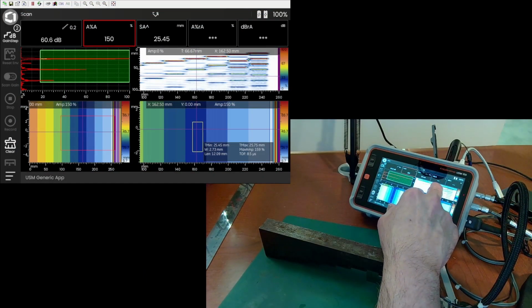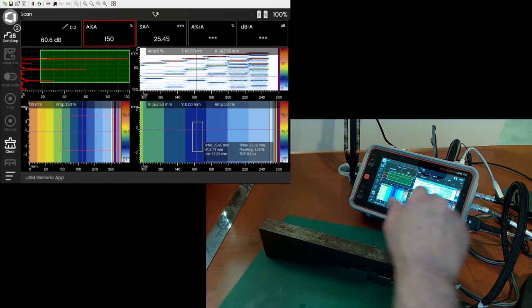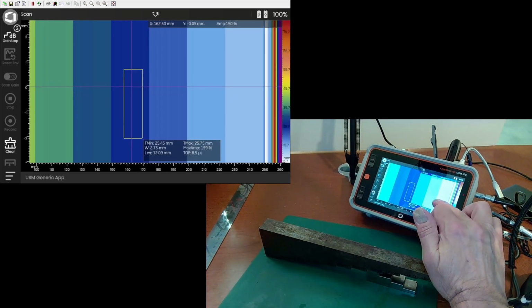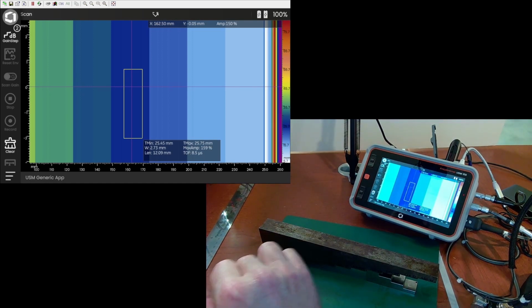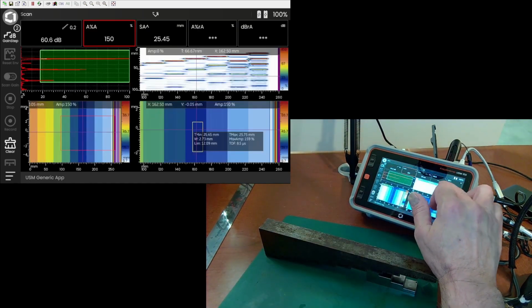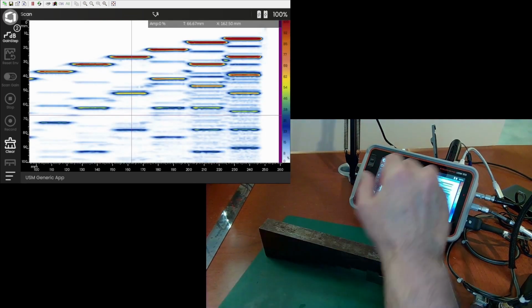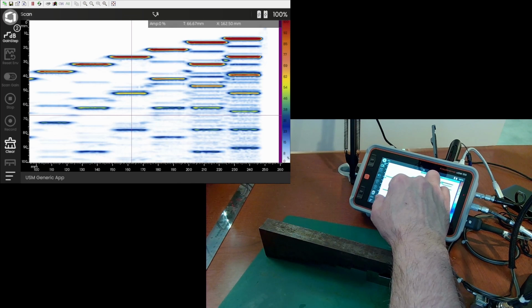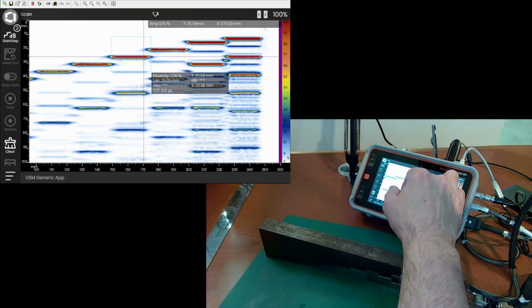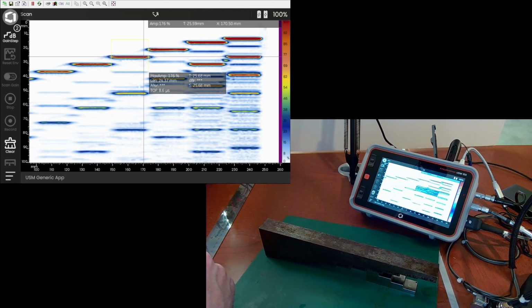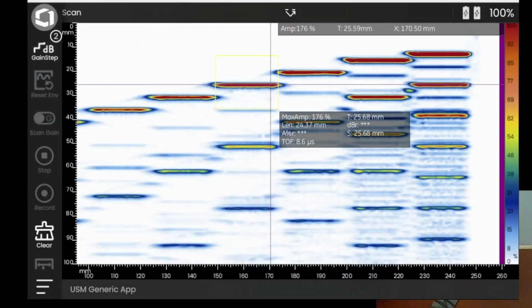If I open any of these views, they can be blown up to full screen by double tapping on them. Okay, there's the active CSCAN taken to full screen. Take the BSCAN to full screen. The BSCAN also has some very useful box tools. I can draw a highlight box around one of the steps. Again, I can see the thickness to that step. I can see the length of the box. There's amplitude information, all of that displayed. And again, the crosshair is going to go to the highest amplitude reading in a box.